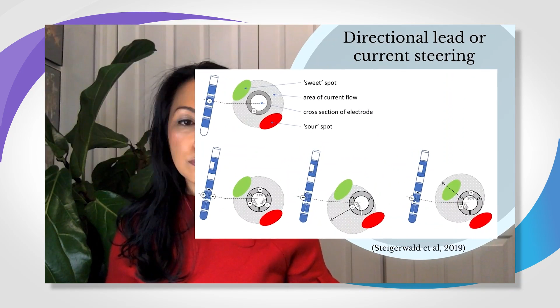So, directional leads. Here on top, you can see that the green spot is the sweet spot. The red area is the sour spot where we're getting side effects from stimulation, and the gray area is the area of current flow around the electrode, and this is a cross section of the electrode.